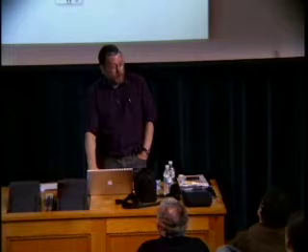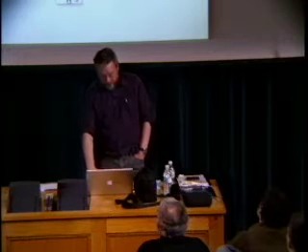As I built the simulation of the Graseby 3400 pump, every so often I came across a strange feature, like it's got timeouts. And there are other strange features in it. Why are there timeouts? Well, I don't know. So here is my list of 38 queries I had. To me, as an HCI person, I thought these were odd decisions in its design. But I don't know much about how people use syringe pumps in reality. Maybe there's a good reason for having timeouts.